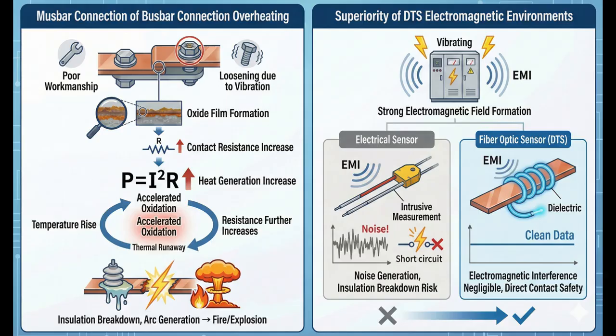Busbar overheating typically starts at connection points. If bolts loosen due to poor workmanship or vibration and oxide films form, contact resistance increases.